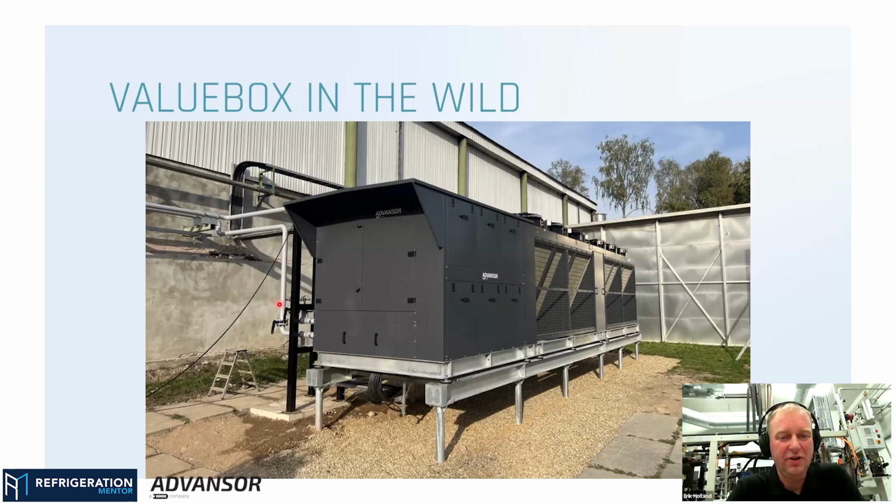It'll basically take you weeks, because you have quite a lot of volume in there. If you've been unfortunate enough to get water in a pipe from production, where you cool the pipe down and it's not dried properly afterwards, or some external installation with open pipes where moisture gets in overnight, then you have an issue with water in the system. It's a pain to get rid of.